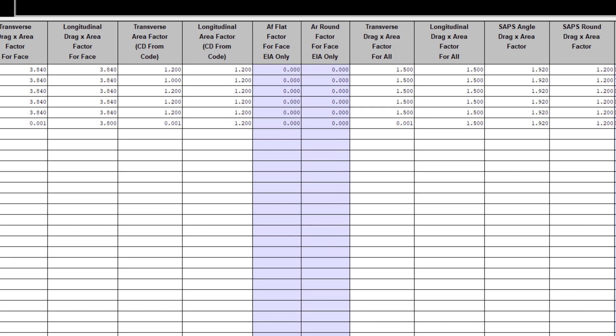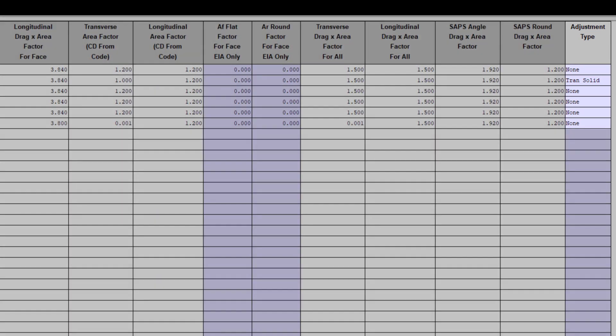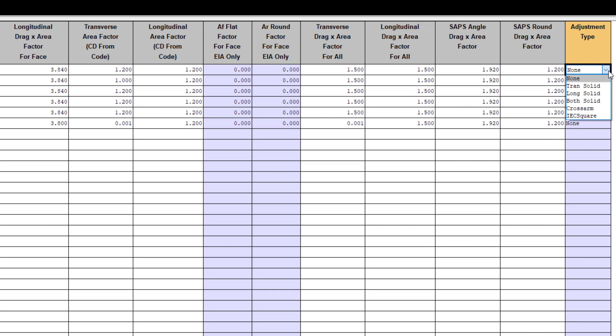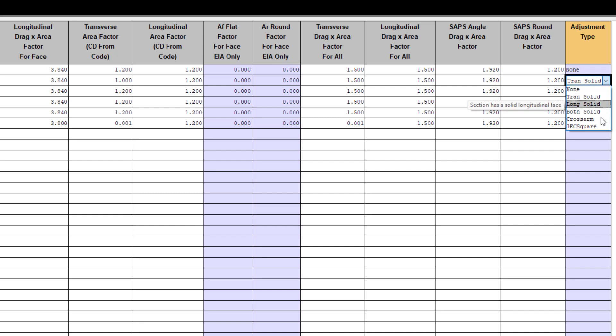The very last column in this table allows for gross area overrides. These allow you to override the wind area of a section to use the gross section area, as if it was a solid area. This is useful for congested parts of the tower, like the bridge or arm of flat configuration single circuit towers. The overrides here that you can apply are for the transverse face, longitudinal face, or both.